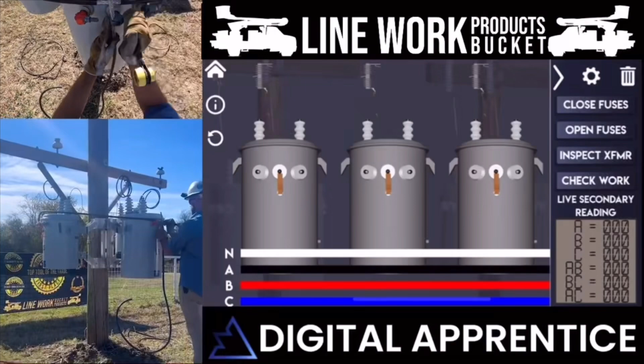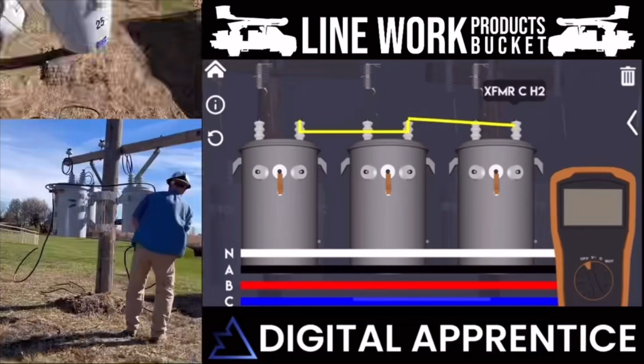The first thing you want to do is get your neutrals bonded. So you run your two outside transformer connections to the center phase. And then here you can see that I took that center transformer leg and shaped it to where I put this one bolt on there and I connect all my neutrals at the center pot. This makes it a lot easier to identify the neutral when you're doing trouble work, and it makes the transformer bank look a lot cleaner. And I'll show you why as we put these hot legs in.